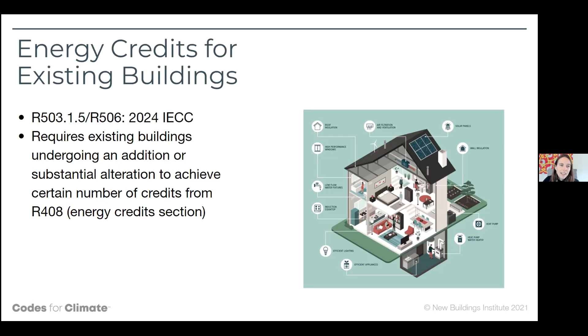This is a new section in the stretch code and in the 2024 IECC that says if you have an alteration where more than 25% of registers or total length of ducts are relocated, or the duct system itself is increased by 25%, then you have to do duct testing. You don't have to do balancing, but you do have to do duct testing.